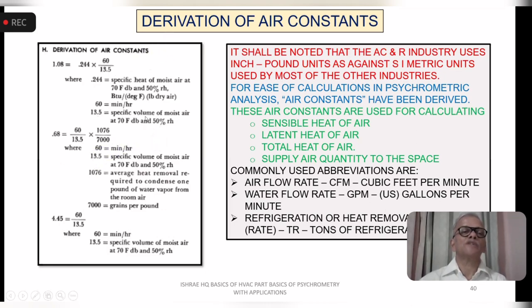And then 13.5 is the specific volume of the moist air at that temperature, 70 degrees Fahrenheit and 50% RH. That is taken as the mean or the center point, the most common of the two ends of the AC system temperatures required. And that is the standardization. If you see this 1.08 in the Carrier method, when you go to the ISHRAE method, you will find this constant as 1.1. For latent heat, in a similar manner, you have taken 60 minutes to 1 hour and the specific volume. And this 1076 is the average heat removal required to condense 1 pound of water vapor from the room air. So this 1076 is the heat removal requirement.